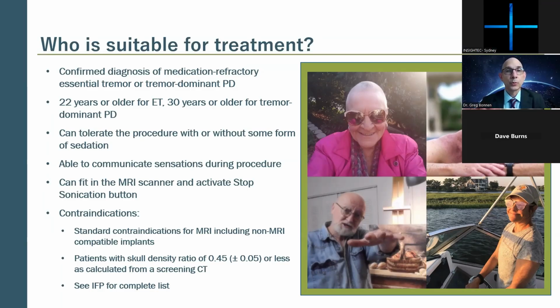Perhaps the single most important thing that we have to evaluate is just how well the ultrasound energy is going to be able to transfer across the skull toward the target. And we've got a calculation, something called a skull density ratio, that allows us to get a good measure of how efficient the skull will be with the ultrasound. It's not the only factor that contributes to efficiency, but it's the single most important one, and it's the one that we look at. So the FDA actually has established a threshold of 0.45 plus or minus 0.05, meaning the skull density ratio really needs to be 0.40 or above in order to qualify as being an on-label use of the treatment.